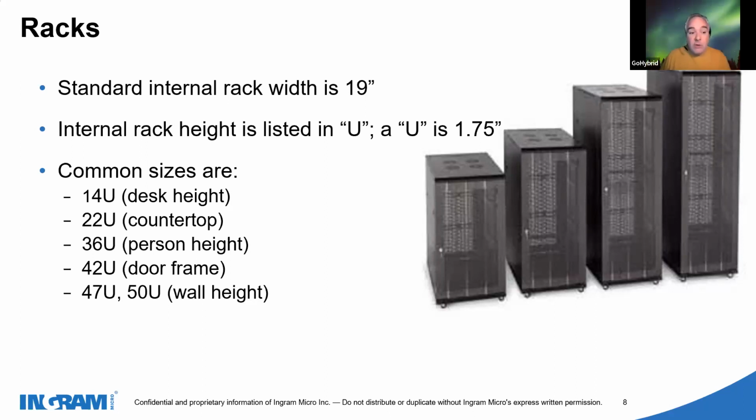If you're going to have 47U or 50U racks, you need to have a door on your data center that is 47U or 50U tall that leads right out to your loading or your receiving dock, or multiple doors. All the doors along the way to your receiving dock essentially have to be 47U or 50U in height, which is a non-standard door. These things are massive enough, typically between 350 to 550 pounds. You are not going to tilt them and gently slide them under a door at an angle. They do have wheels on them to move them into place. But again, you're not going to tilt them and take that weight off of 4 wheels and put it onto 2, because you will crush the wheels and then the rack will crush you.